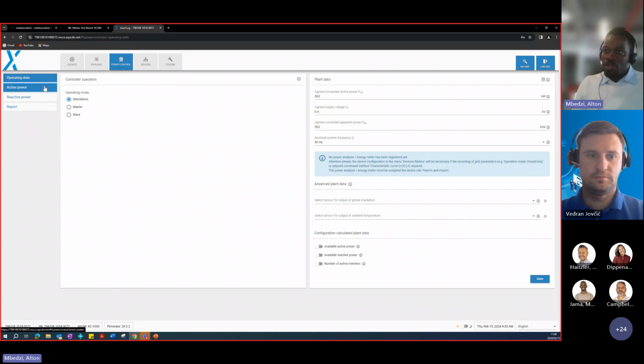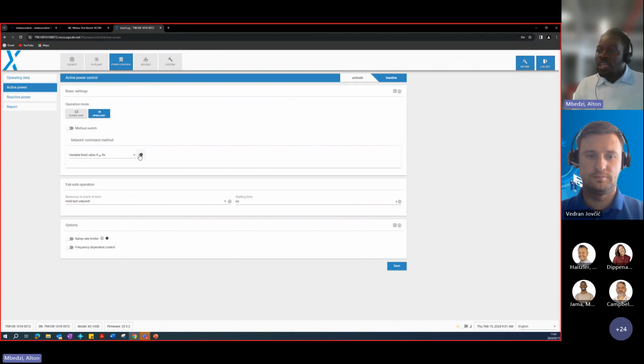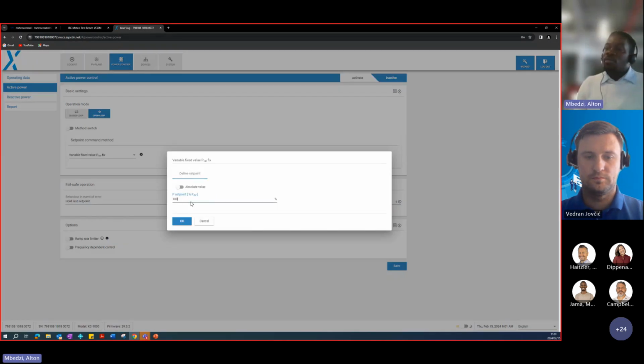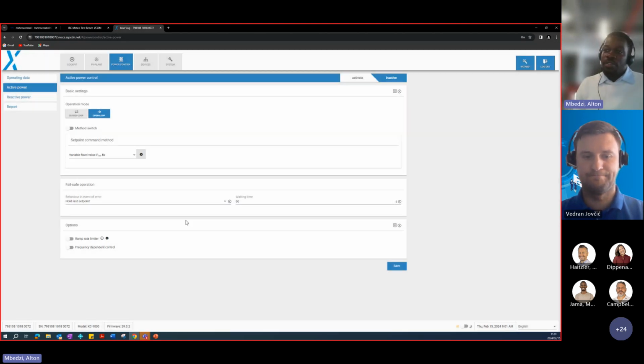Maybe just another thing to mention, it's not just the generator we have. If you only have, for instance, a grid type, same scenario. Let's go here, load, you would say okay, you stay there. And then you set the set point, that would be 0 — sorry, not 100, 0. You put it on 0, and then zero feed-in is enabled, and then you just save it. So for each and every scenario, there's a different way of setting up your system, but always feel free to ask if you're not sure and want assistance commissioning the site.